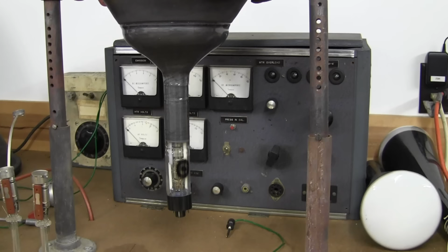And there are a couple of ways it can be done. Sometimes you can reactivate them simply by running the heater of the tube itself to heat it up to the temperature to activate it. Other designs of guns would require, again, an inductive external heating source to achieve the same result. And so what we're doing there is watching the performance of the tube while we're doing this process to make sure that we don't overheat the getter. Sure. Yes.